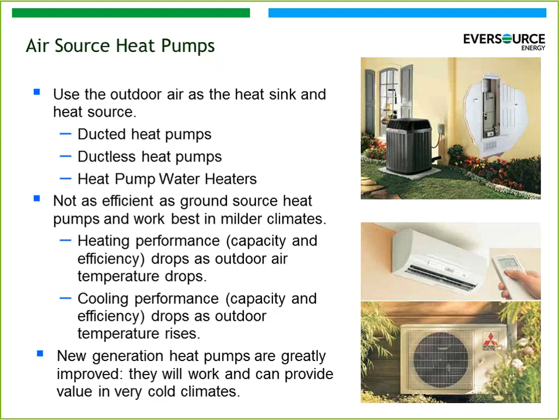Now, most of you have probably heard about some of these newer generation heat pumps and newer generation ductless heat pumps. They are greatly improved compared to heat pump technology 10 or 15 years ago, and they can provide value in cold climates, but they're still not 100% perfect. When you get to temperatures below 10 or 15 degrees or 5 degrees, in most cases, there are exceptions, but in most cases around 10 or 15 degrees is the critical point where the heat pump may not quite be able to keep up with the load, and you're going to have some type of backup system to provide the difference.